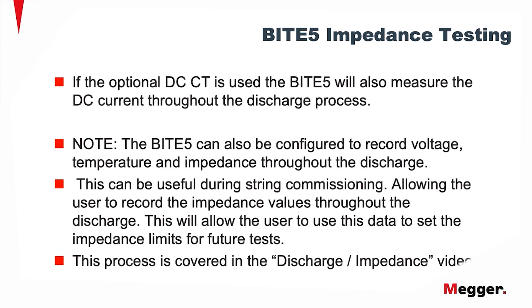Note: the BITE5 can also be configured to record voltage, temperature, and impedance throughout the discharge. This can be useful during string commissioning, allowing the user to record the impedance values throughout the discharge. This will allow the user to use this data to set the impedance limits for future tests.